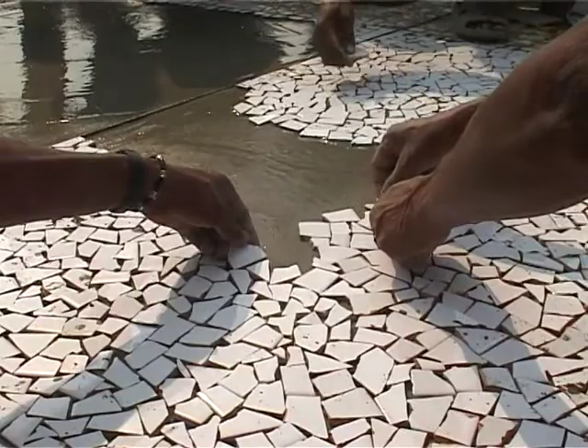An important decision was the range of temperature we felt we could tolerate. Instead of a standard AC 5-star environment of 22 to 25 degrees centigrade, we said we can go down to 18 or 19 degrees. When it's very cold, we put on a sweater - it's okay. When it's hot for a few days, 30 degrees is fine, and we're all wearing half-sleeve t-shirts anyway. We're comfortable tolerating that, and it's a lifestyle statement we want to make.